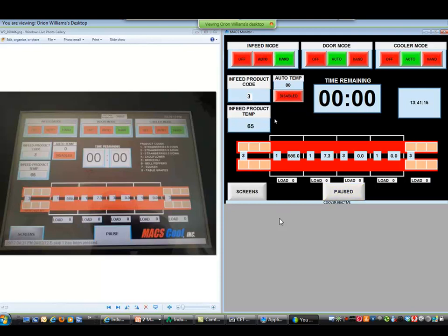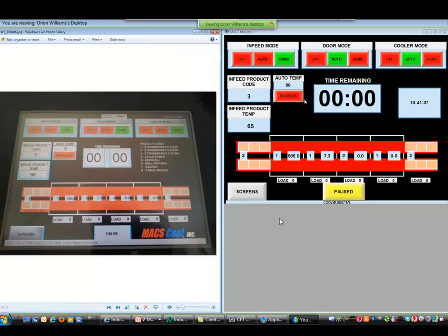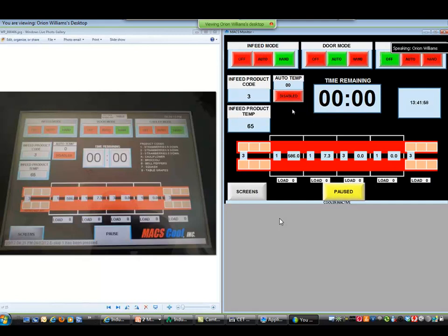All these values are adjustable. On the real cooler, if I press the door mode button, you can see you can go to 'off' and the door mode would go to off. If I press the cooler mode off, then you'd see on the Web Studio application the cooler go to off. This works because they all address the same PLC registers — we use a Koyo PLC, and the drivers in Web Studio are synced to the PLC. If you write to them from Web Studio, the screen reads from that same address the new value. If you enter a new value in the screen, Web Studio polls the PLC and retrieves the new value.